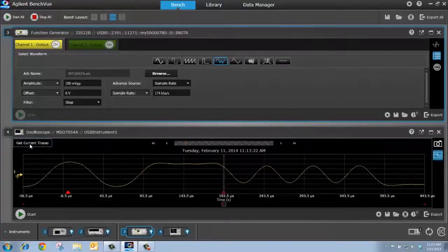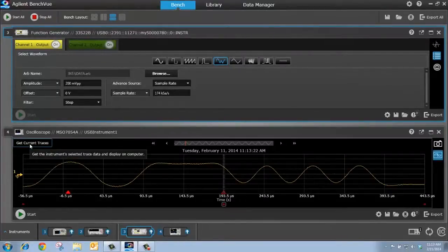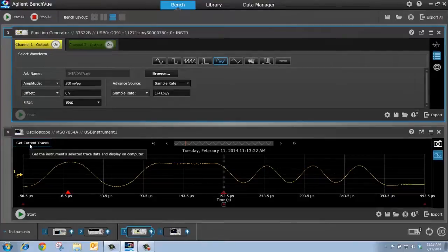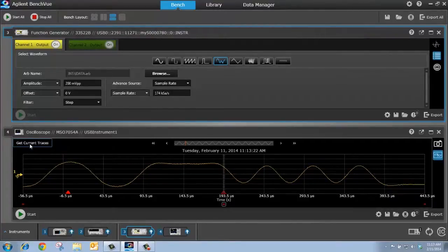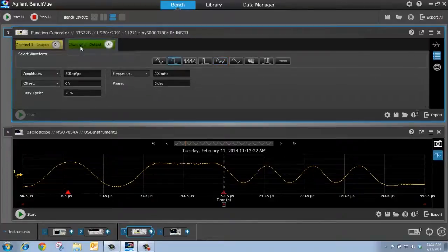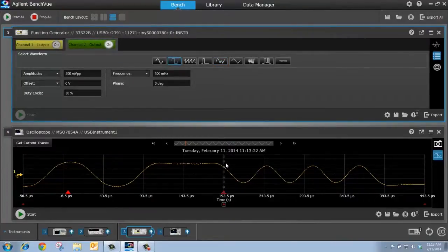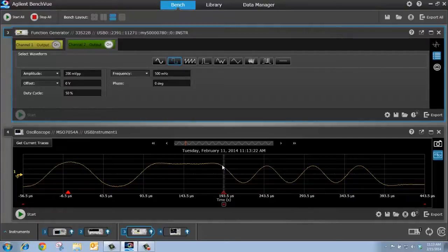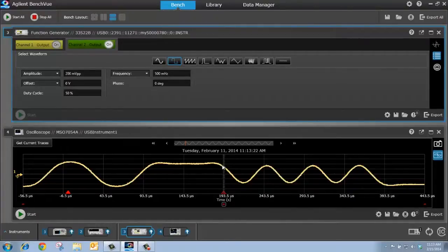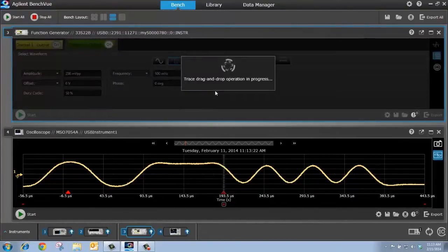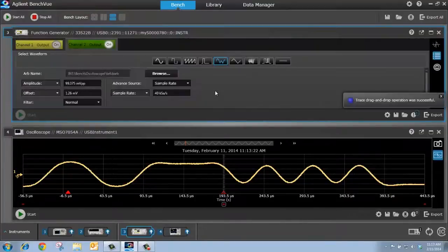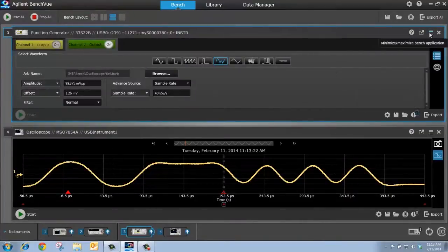Now, this is going to capture the trace data on my scopes, so the digitized points on my scopes, it captures it in bench view. I'm going to go to channel 2 of my function generator, and to turn this scope signal into an arbitrary waveform, I can simply highlight it and drag and drop it to channel 2 of the function generator.